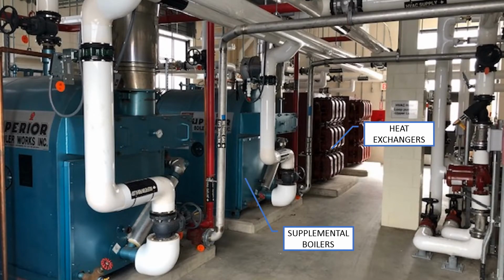Within the heating room portion of the digester equipment building are a series of pumps and pipes, but the 2 most important pieces of equipment here are our supplemental boilers and our heat exchangers. Because the digester needs to be maintained between 95 and 98 degrees Fahrenheit, there's a fair amount of heating that needs to take place to this material. The heat exchangers are constantly being fed material from the digesters, and heat is circulating through that system at all times. The boilers are a backup heating system if we are unable to extract enough heat off our combined heat and power units.